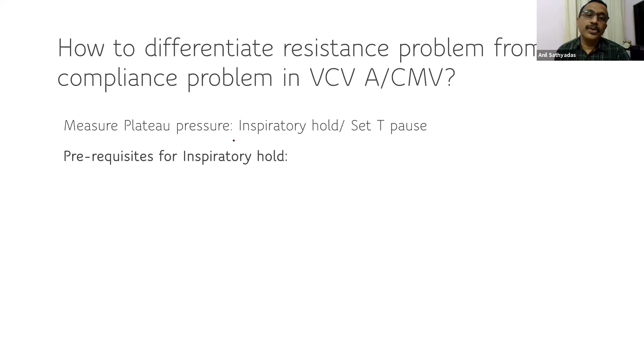I told you, inspiratory hold. Yes, you can press it. There's a button written as inspiratory hold. Or the second option to get the P plat is to set a T pause. On the ventilator setting, you have an option for T pause. You can set it as 10 to 15%. So every breath, 10 to 15% of the inspiratory time would be spent as a pause, and the P plat would be shown on the ventilator screen. You don't have to go there and press the inspiratory hold button every time.